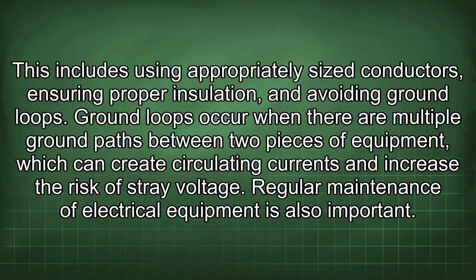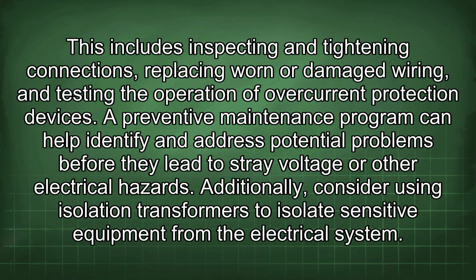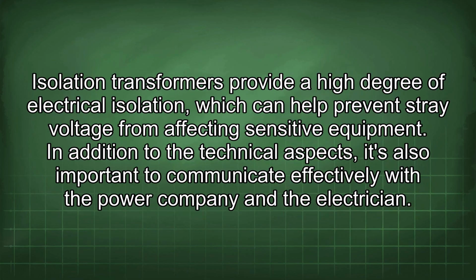Regular maintenance of electrical equipment is also important. This includes inspecting and tightening connections, replacing worn or damaged wiring, and testing the operation of overcurrent protection devices. A preventive maintenance program can help identify and address potential problems before they lead to stray voltage or other electrical hazards. Additionally, consider using isolation transformers to isolate sensitive equipment from the electrical system. Isolation transformers provide a high degree of electrical isolation, which can help prevent stray voltage from affecting sensitive equipment.